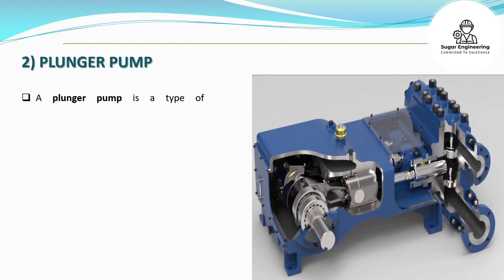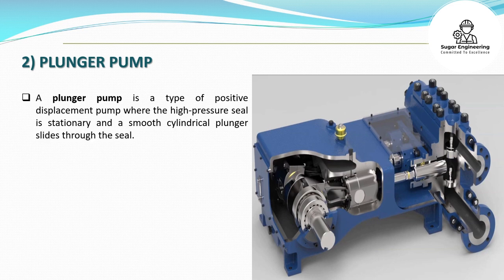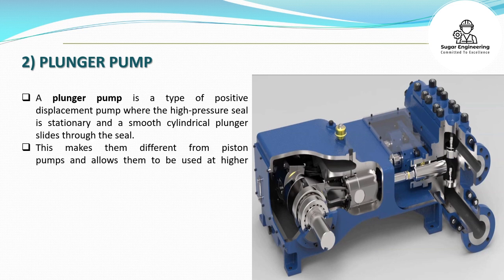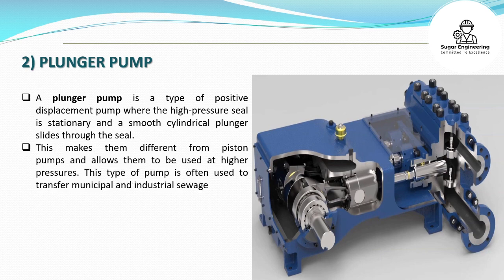2. Plunger Pump: A plunger pump is a type of positive displacement pump where the high-pressure seal is stationary and a smooth cylindrical plunger slides through the seal. This makes them different from piston pumps and allows them to be used at higher pressures. This type of pump is often used to transfer municipal and industrial sewage.